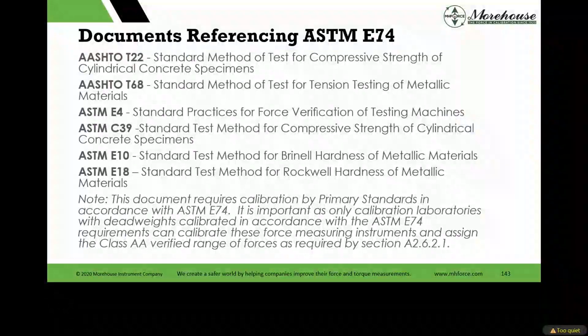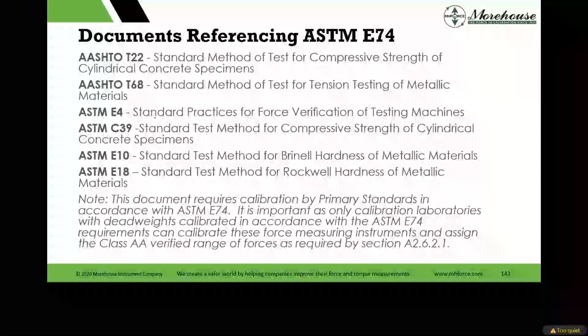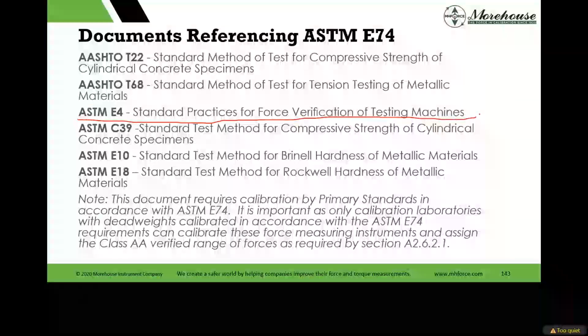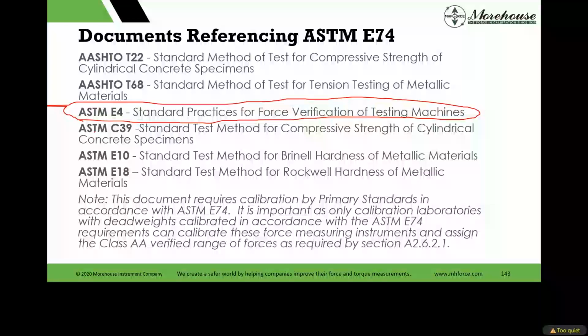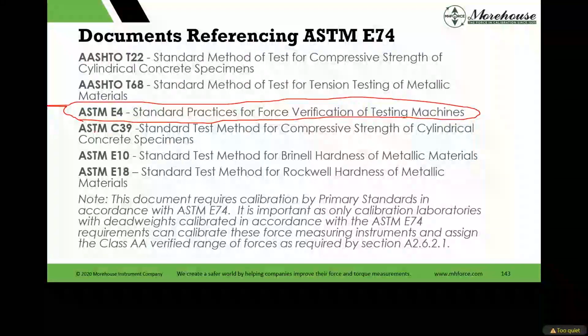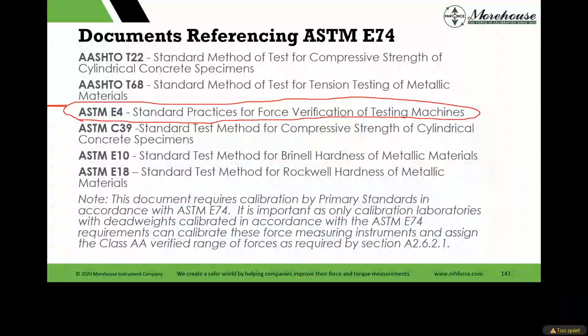More words, descriptive terms. So even if you're not calibrating to E74 or your company doesn't require it, there are standards that may come into play that reference E74, AASHTO T22, T68, E4, of course. Probably have some people here that are testing the testing machines, or they're using ISO 7500, but that doesn't reference E74. Though for the errors that we're going to talk about later for that group, that'll be beneficial because the errors on our end on the calibration side certainly apply to the field side, right?